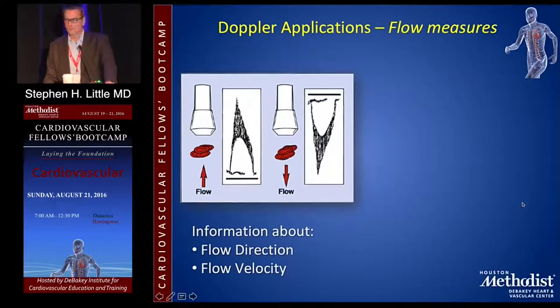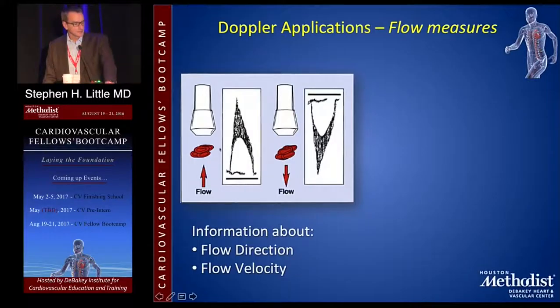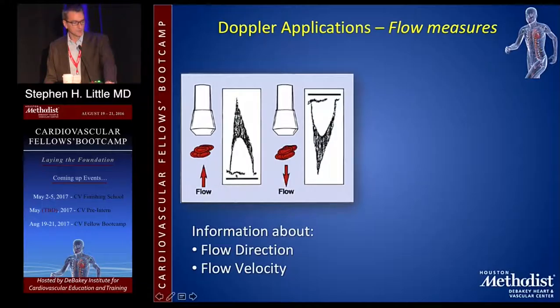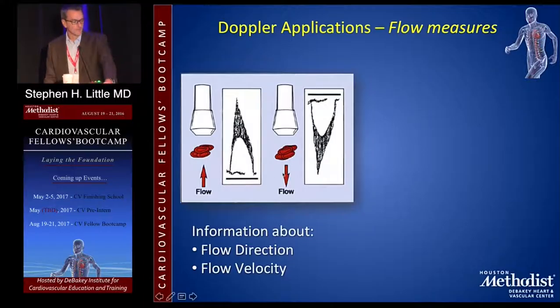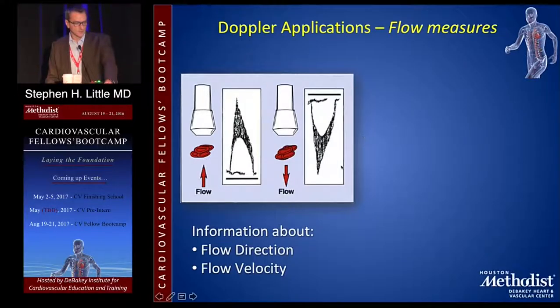For Doppler applications: the probe detects red blood cells moving towards it, and this is displayed on pulse wave Doppler. Time is across the bottom, and the waveform represents a population of blood cells moving in. The more this looks like a thin line drawn by a pencil, the more uniform and laminar the flow. We get quantitative information from Doppler about the direction and velocity of flow.